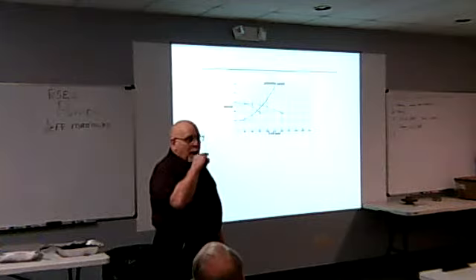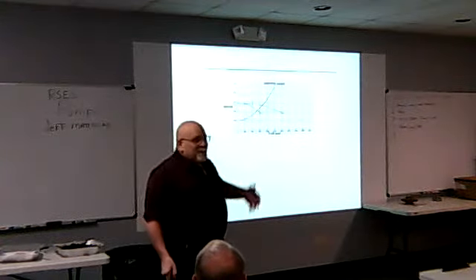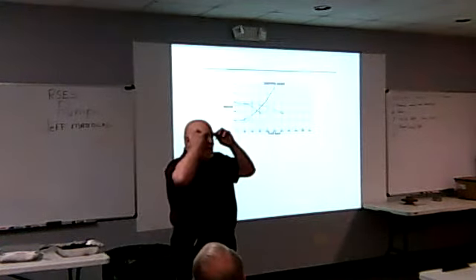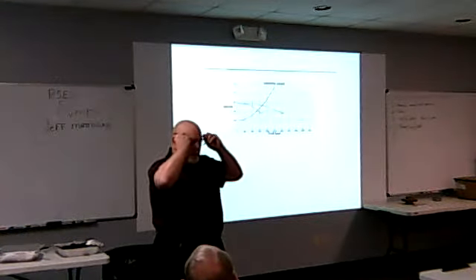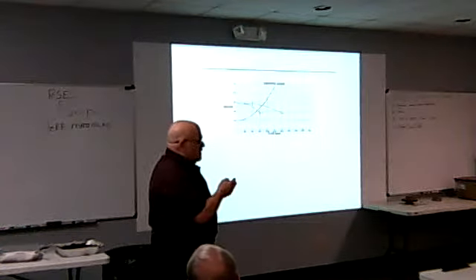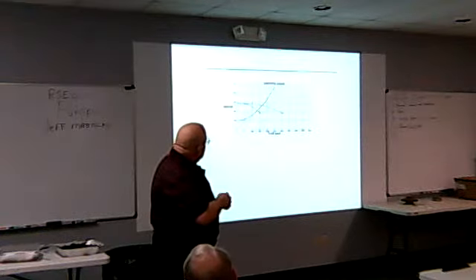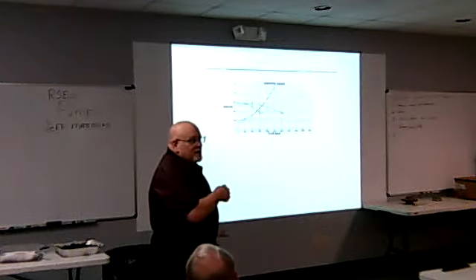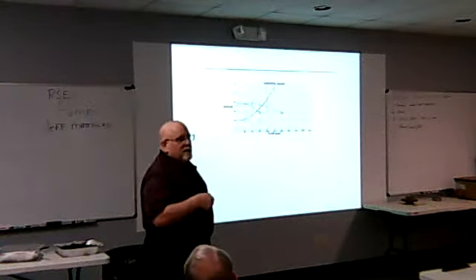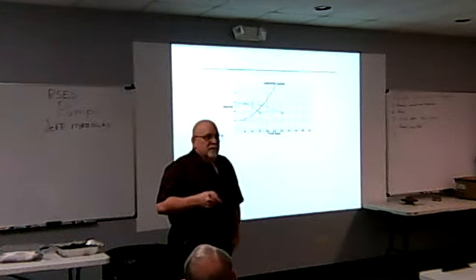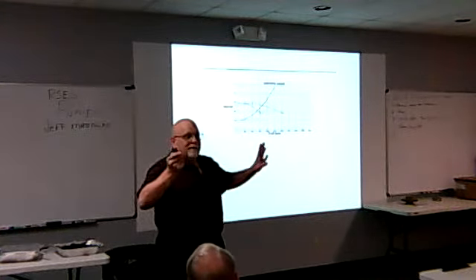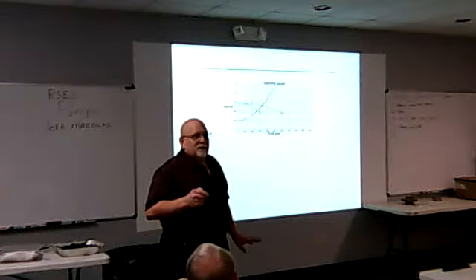But if you doubled all your pipe sizes, you probably could change your pipe size to get the head back to where it originally was. You can do a lot of other things, but with our system, we have to be on this system curve. We didn't order it. This is what's limiting us for the increase. Does everybody follow that? Okay? Nobody falling asleep? Am I too boring?